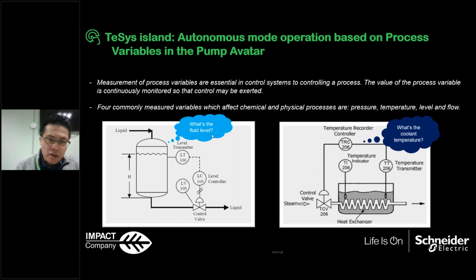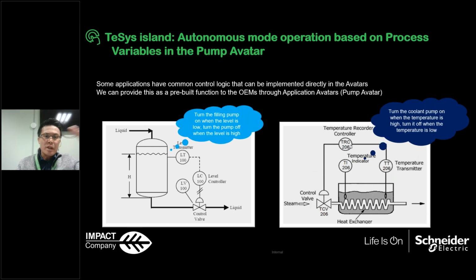So we monitor the fluid level from the sensors, and then the fluid level signal will go as input to the system, to the TeSys island, or you can also measure the coolant temperatures with a different sensor signal as input to the TeSys island. And then by monitoring the fluid level sensors, as I mentioned before, if the fluid level is too low, the pump should be kicked off automatically. And if the fluid level is too high, the pump should stop. And all this can be configured inside the TeSys island.